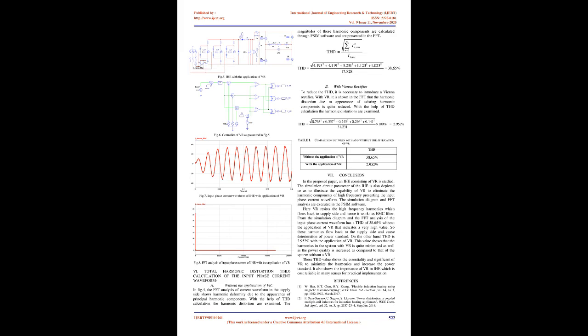It consists of a 3-phase AC source, which is connected to a 3-phase, star/delta, step-down transformer, whose secondary side is connected to a 3-phase diode bridge rectifier. Now the IH coil consists of a series combination of RLC. This combination behaves like a load of the resonant inverter. The simulation diagram has other voltage and current measuring devices such as an ammeter, which measures the input phase current of IHE. It is connected to observe the FFT analysis, which shows the various high-frequency harmonic currents.